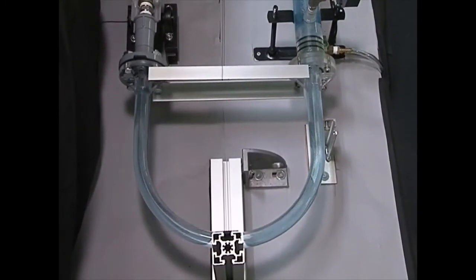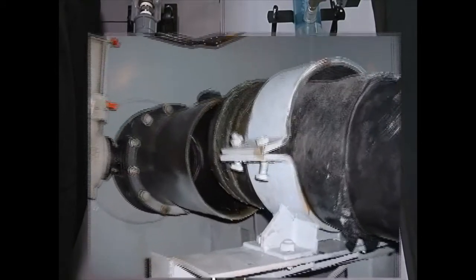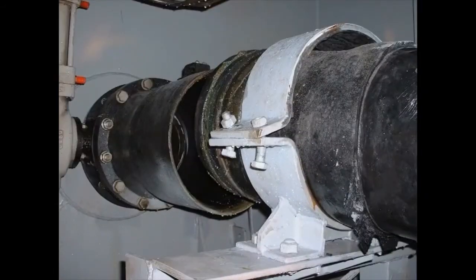The U-tube is movable. When pushed by the water force, it moves back and absorbs the impact. With an actual pipeline, such impact cannot be absorbed fully, resulting in damages such as cracks. Damage to the dresser joint is typical.